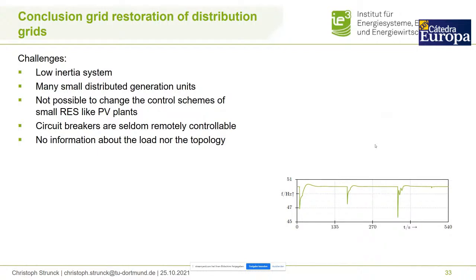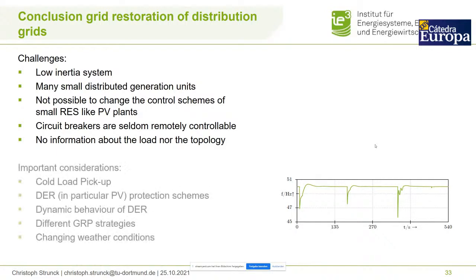Concluding, we have a lot of challenges in the grid restoration of distribution grids. We have low inertia. We have a lot of small distributed generation units. It is not possible to really change the control schemes of small renewables like household PV plants or battery storages. We need circuit breakers that are remote controllable, because if a person needs to drive to every circuit breaker, that takes days to restore the grid. And we often have no information about the load situation or the topology of the grid after a blackout.